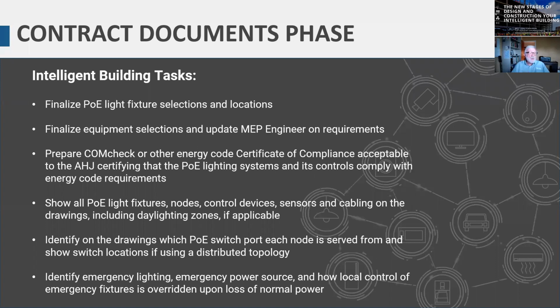And then a really key thing for contract documents is to identify clearly how you're handling emergency lighting. If you heard our first session, I mentioned that when we were doing Sinclair, one of the first things we did was sit down with the AHJ, the chief electrical inspector, and the fire marshal. They identified very few things they were going to require us to do if we were using low voltage DC lighting. But one of the first things they said was, you must comply with all the building code requirements for emergency lighting and egress lighting. That is critical, so be sure that's called out clearly on the contract documents.